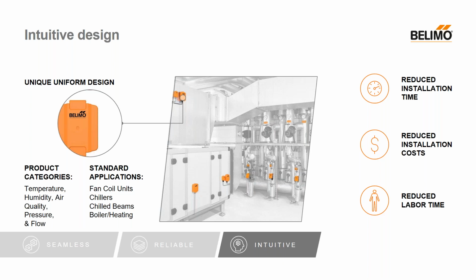He doesn't have to pull out a screwdriver or a screw gun. He can just unsnap it from the mounting plate, do whatever's got to be done, troubleshoot it, look at it, wire it, whatever the case may be, snap it on the mounting plate on the duct and go away. So not only do we make the installation time a little more minimized up front, but for service and maintenance, it's also a whole lot easier to work on a Belimo sensor because of the mounting plate and that snap-on cover.